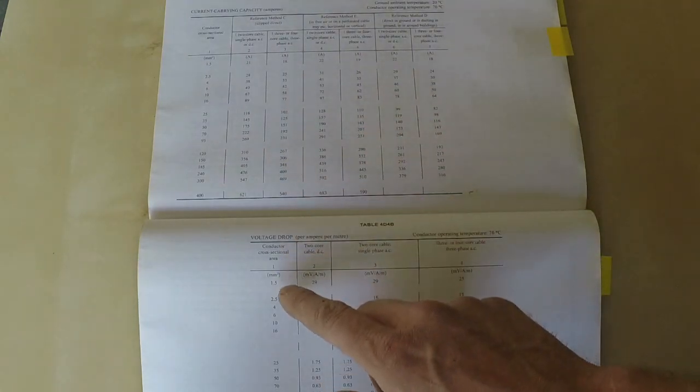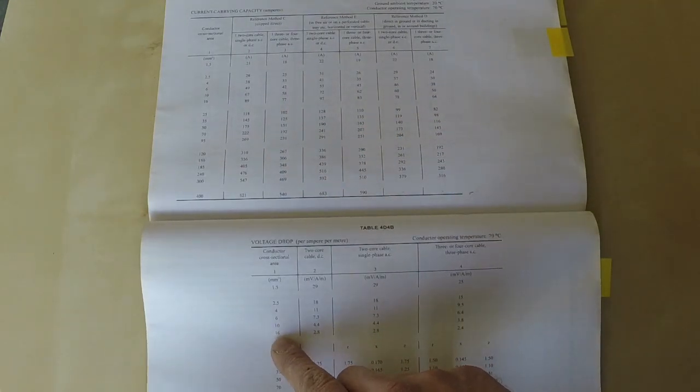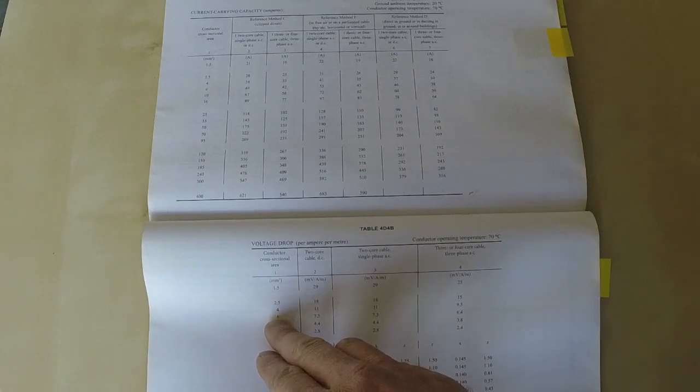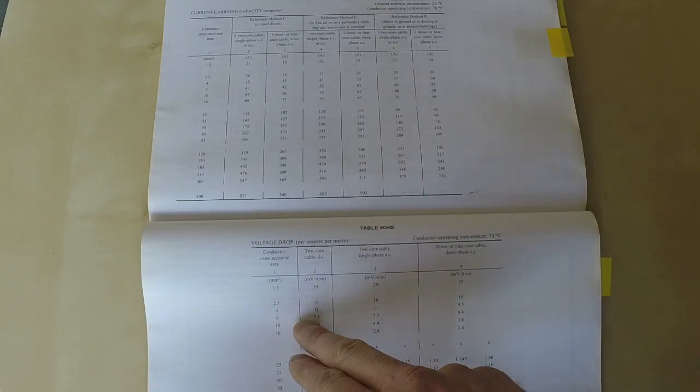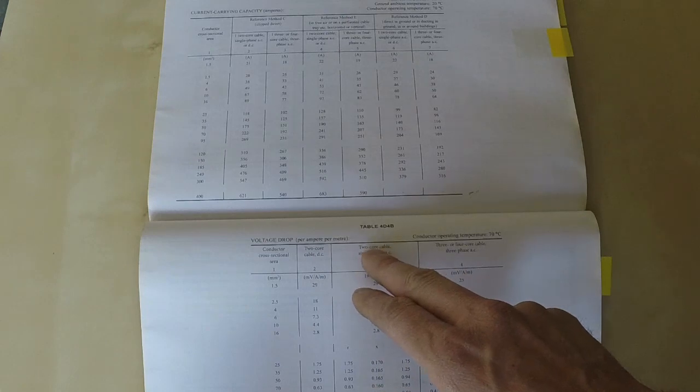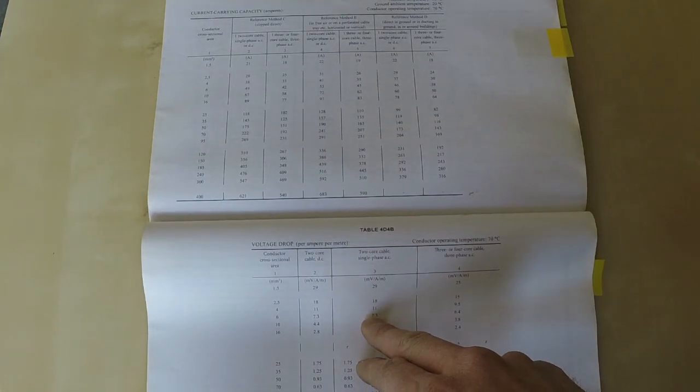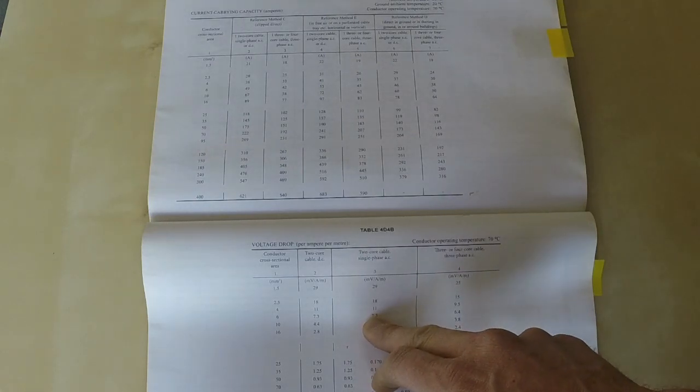Then you go to the table below, which is the volt drop table, and again you find 6 mil and go across to the two core single phase, which is there. That's 7.3 millivolts drop per amp per meter.